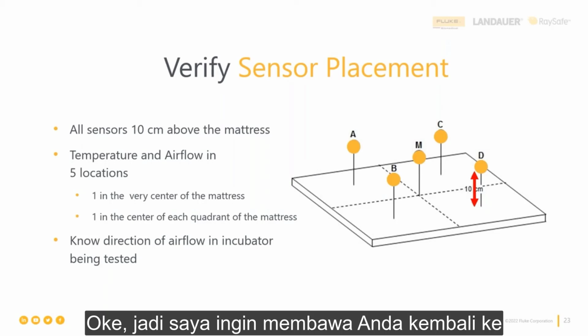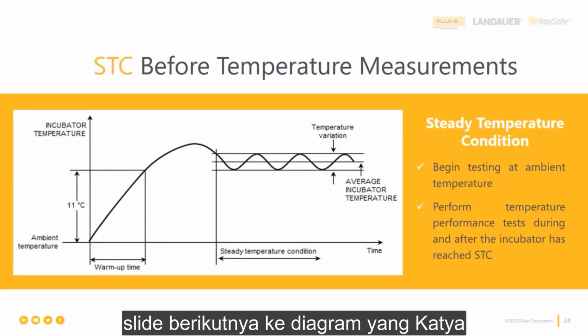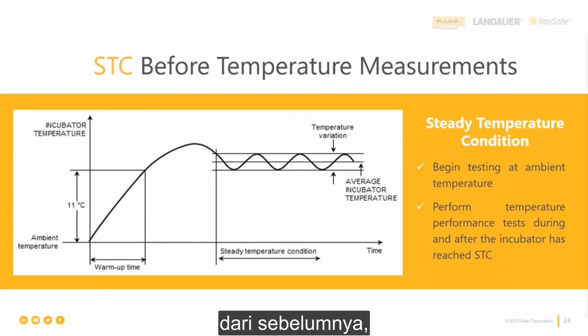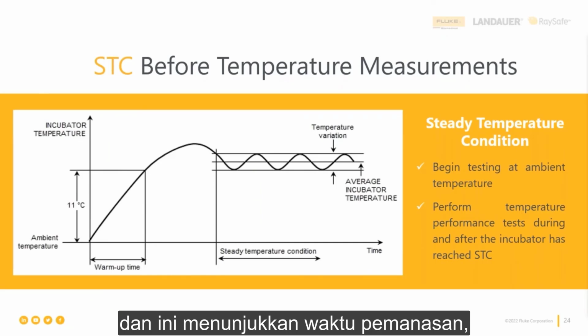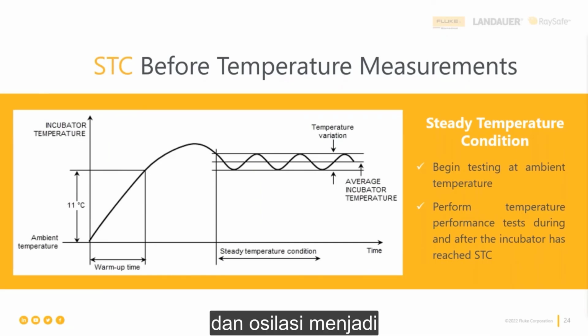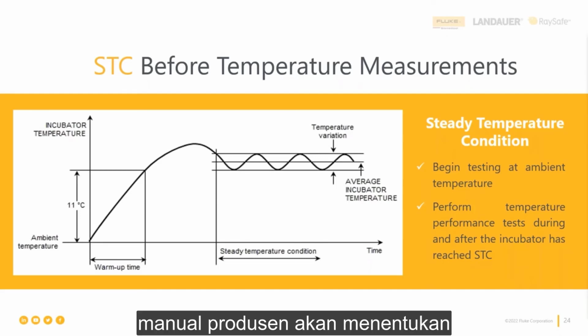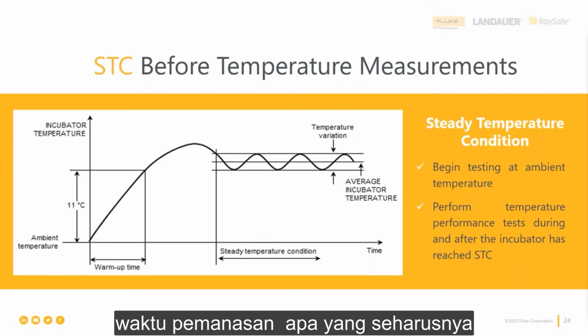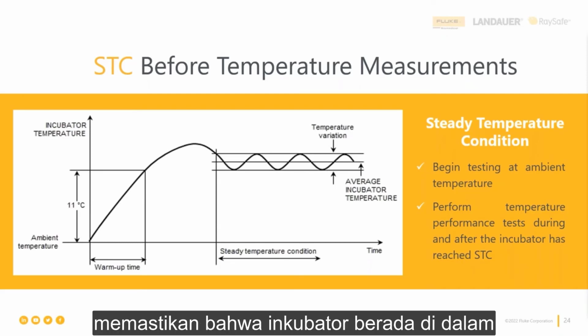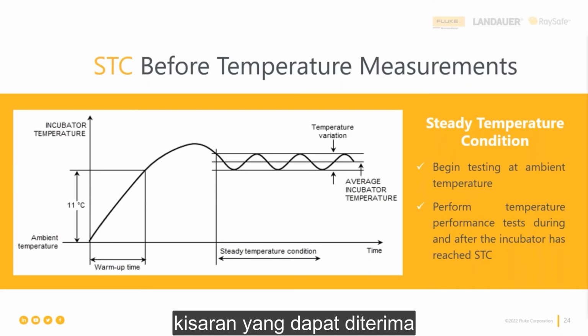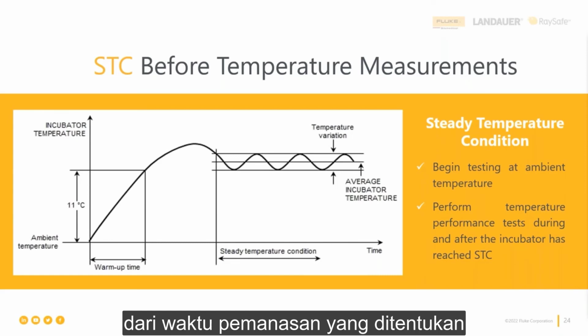Okay, so I want to bring you back on the next slide to the diagram that Katya walked you through about STC. So you'll remember this from earlier today. And this shows the warm-up time, the overshoot, and the oscillation to a steady temperature condition. Manufacturers' manuals will specify what that warm-up time is or should be. And testing should be carried out to ensure that the incubator is within the acceptable range of 20% of the specified warm-up time.